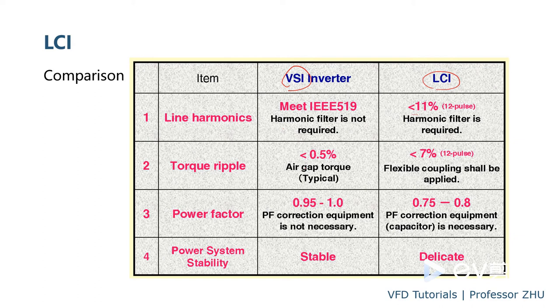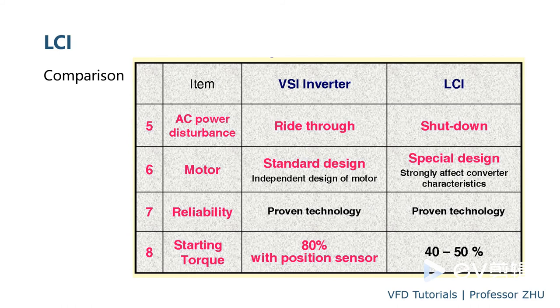And torque ripple. VSI uses PWM technology. So output current waveform is very good, very sinusoidal. But this one is a trapezoidal waveform. So the torque ripple is very high. Power factor, as we said, because of the diode rectifier. And LCI uses SCR rectifier, because of the lagging of the current on the input side. So power factor is also low. And power system stability, big difference.